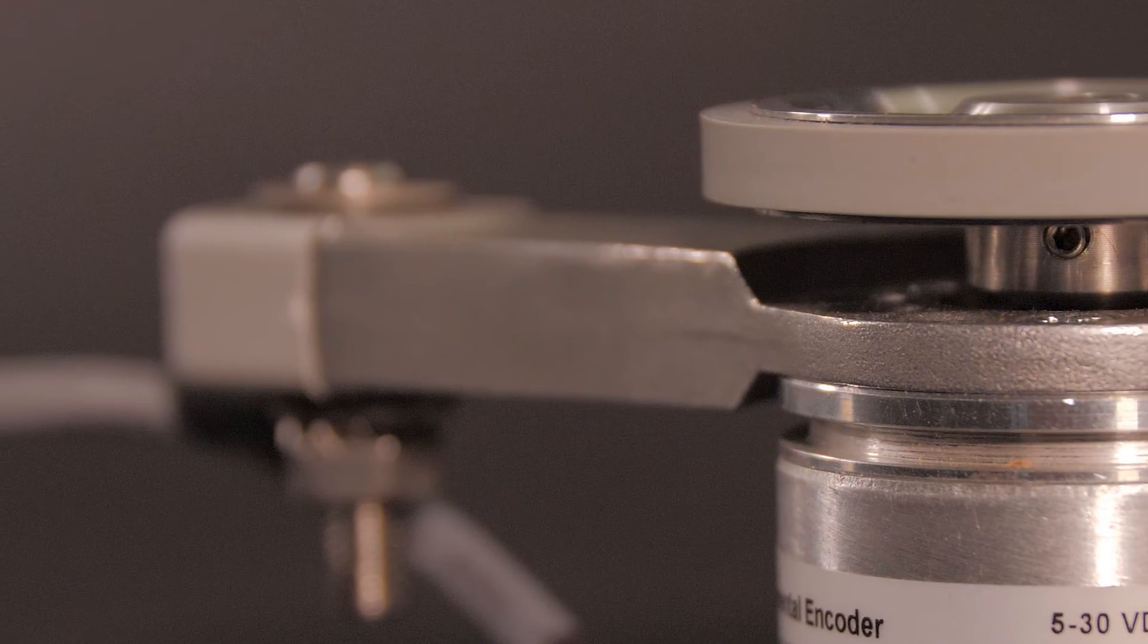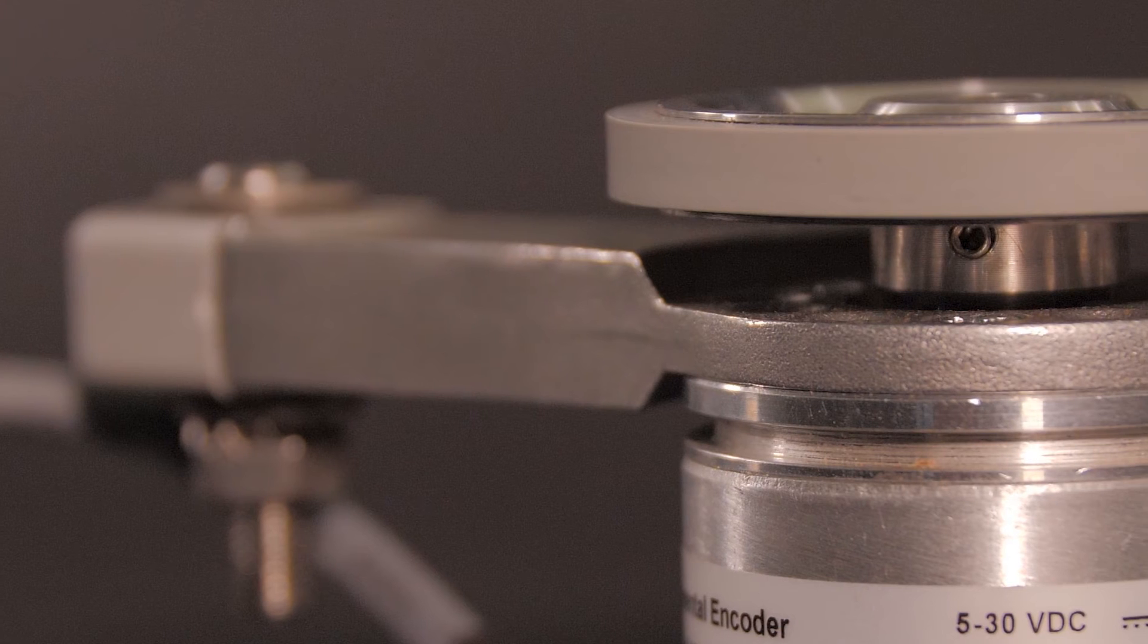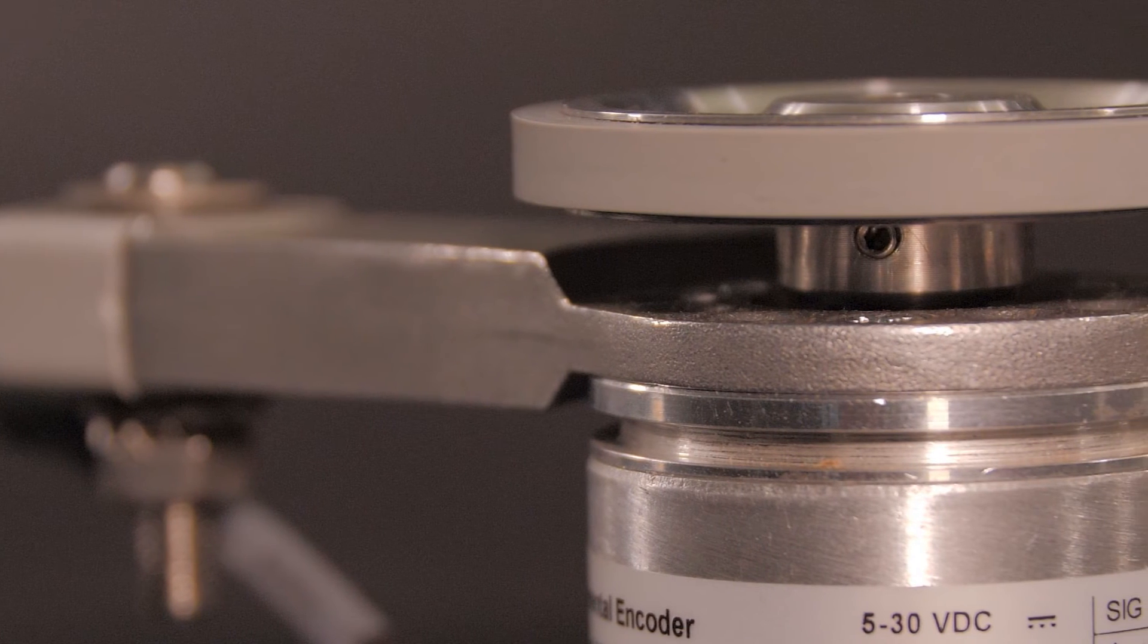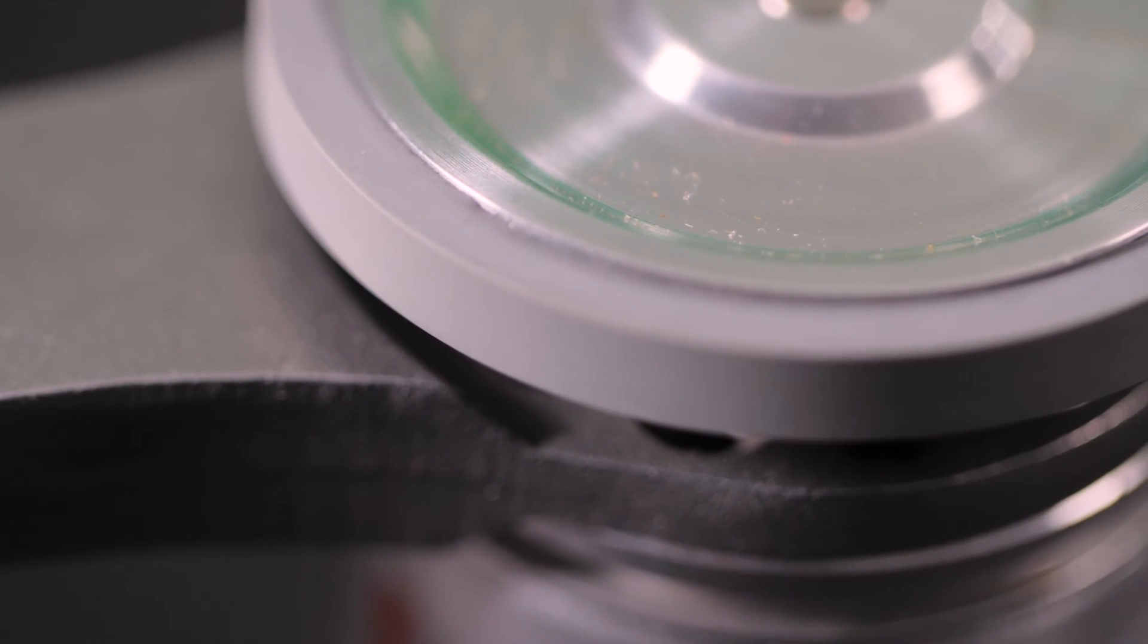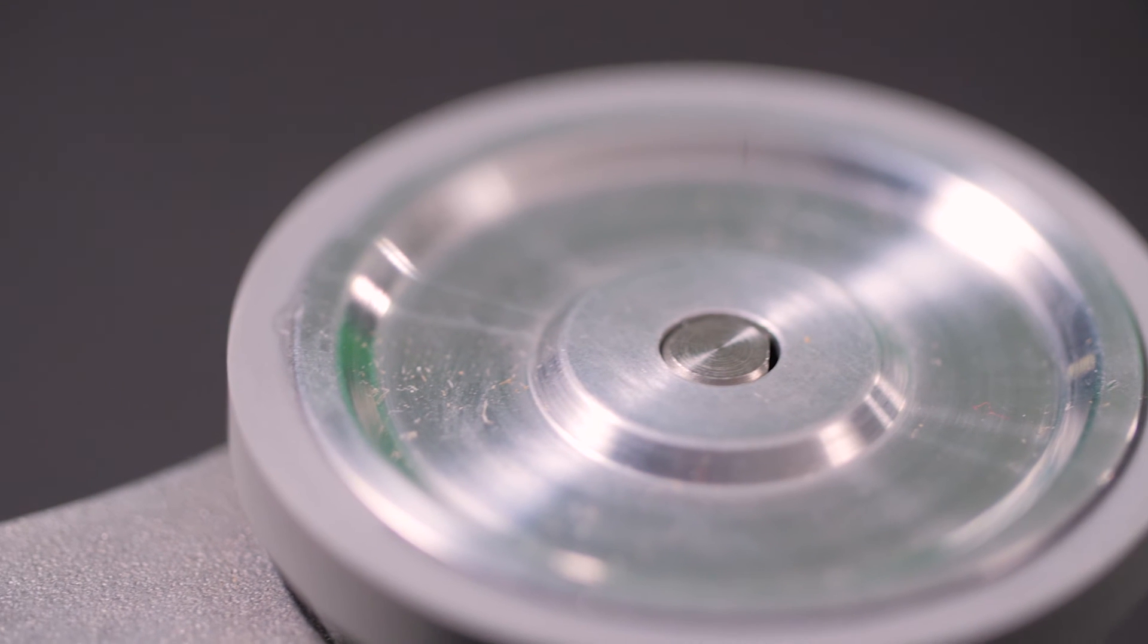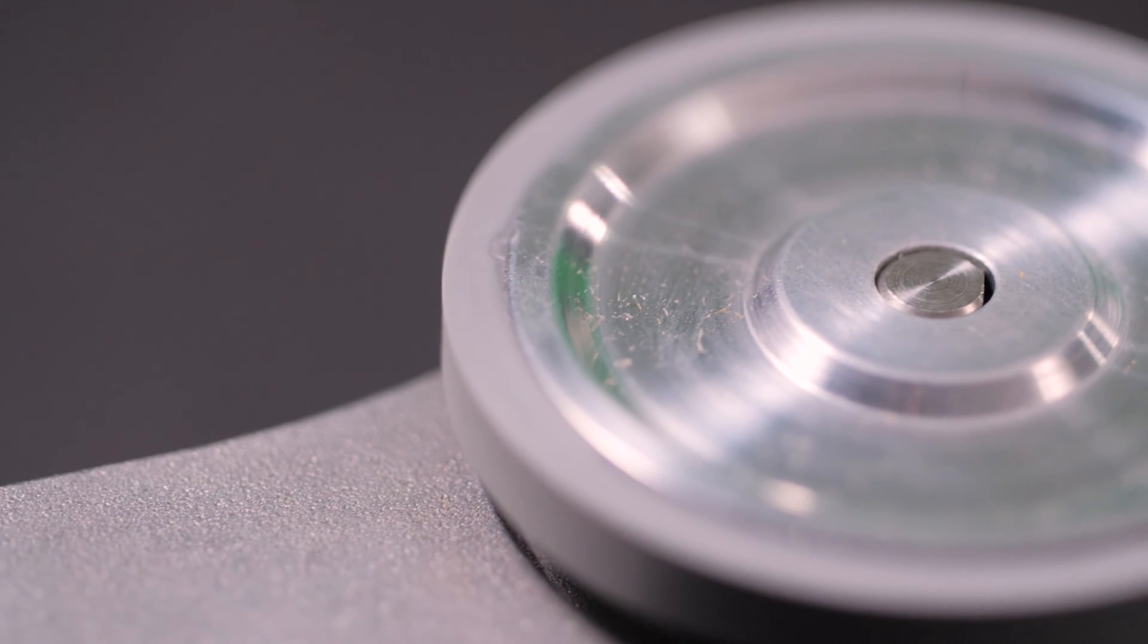The MWE-02 incorporates an incremental Sendix KIS-40 encoder. It features high resolution of up to 2500 pulses per revolution and a maximum speed of up to 4500 revolutions per minute, which also ensures maximum precision and dynamics.